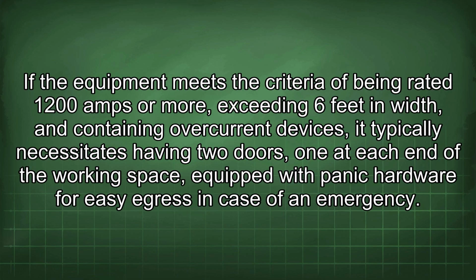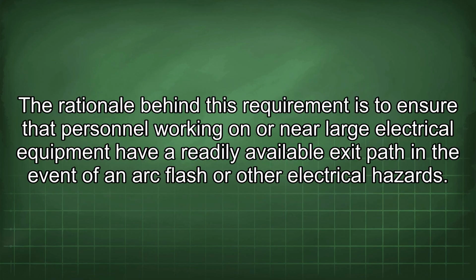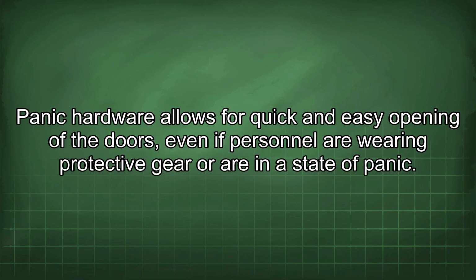If the equipment meets the criteria of being rated 1200 amps or more, exceeding 6 feet in width, and containing overcurrent devices, it typically necessitates having two doors, one at each end of the working space, equipped with panic hardware for easy egress in case of an emergency. The rationale behind this requirement is to ensure that personnel working on or near large electrical equipment have a readily available exit path in the event of an arc flash or other electrical hazards. Panic hardware allows for quick and easy opening of the doors, even if personnel are wearing protective gear or are in a state of panic.